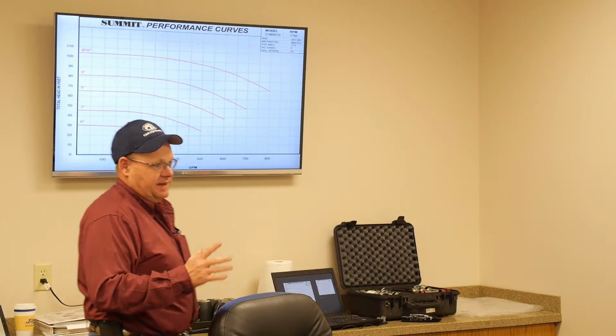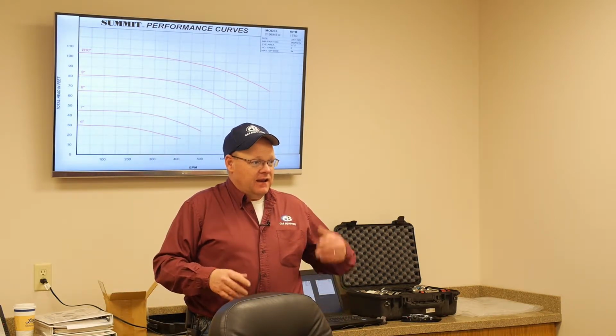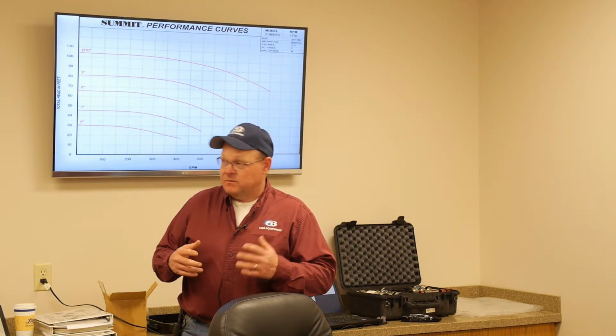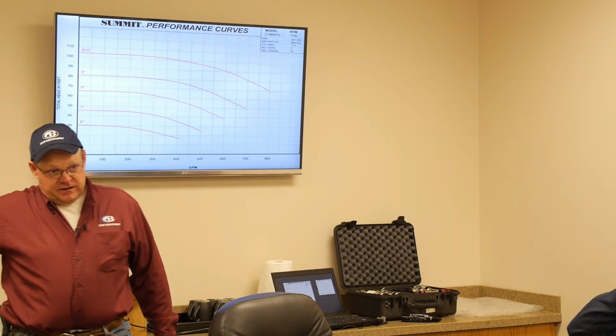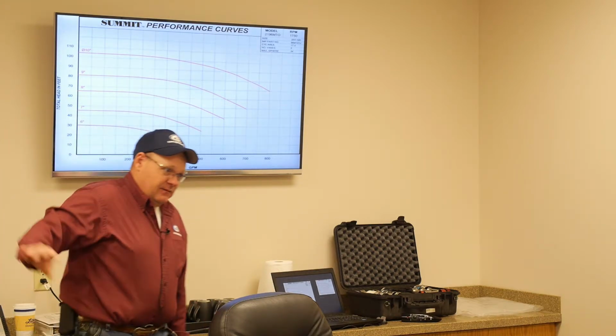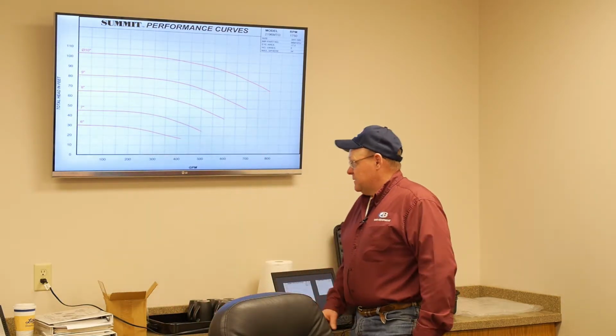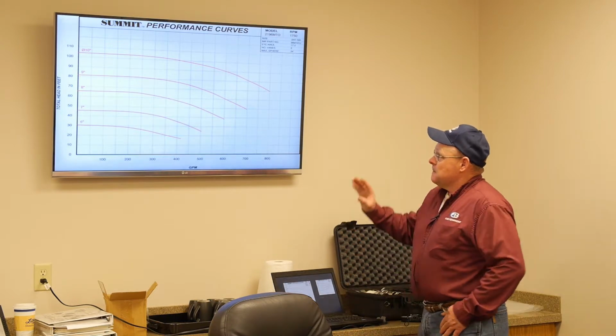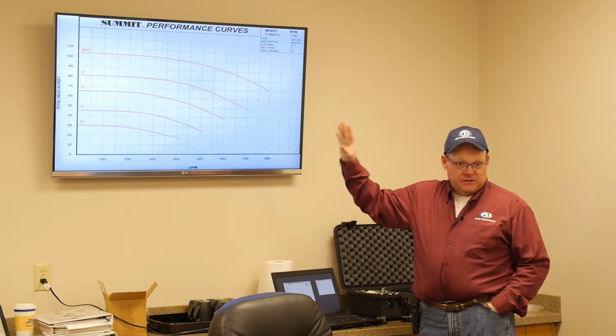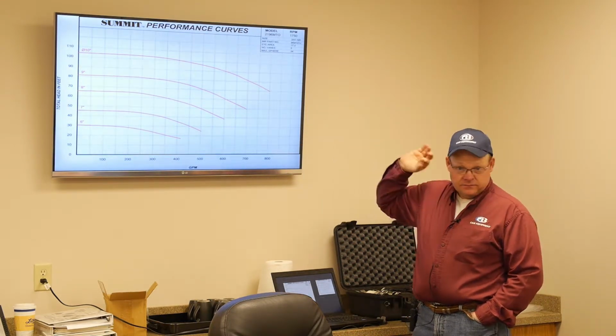Back in the old days, this is how we had to work. Somebody called up and said, I want a pump that does 600 gallons a minute at 25 PSI. So you had to go back: 25 PSI times 2.31 is about 60 feet of head. We had to go over here and find it and get a kind of rough reference point. And then you had to go back and it gets really confusing. But you guys are fortunate. You don't have to do that today. But everybody understands how you can trim the impeller, change the flow and the performance, right?